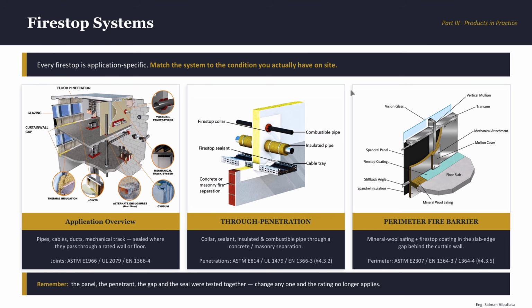The middle picture is a through penetration. You can see the fire stop collar right around here on the combustible pipe. That collar contains a material that expands when heated and crushes the pipe as it melts, and it will seal that hole. Think of it like clenching fists. Whenever things go wrong, it will clench on that combustible pipe. And then you can see the insulated pipe and the cable tray with the fire sealant. That's the most common fire stop on any project. Whenever you go to any project, you should see that.